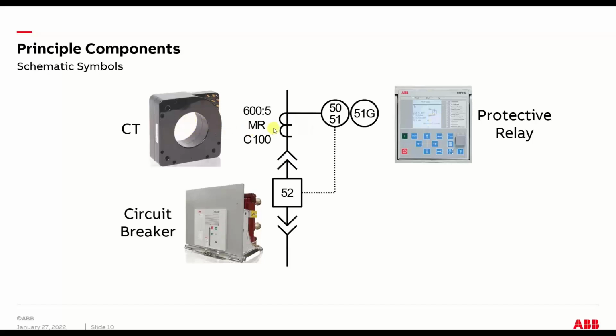CT, here's the actual CT. The ratio on this one is 600 to 5. The 5 on the secondary was historically the default standard secondary CT current in North America. So every CT was something to 5 in North America. Now, if you go into the European market, they had a lot more of the X to 1 ratio. So they used 1 as a secondary current versus 5 in North America.